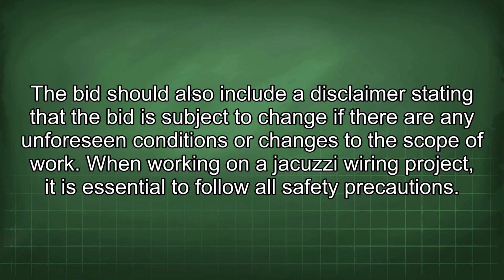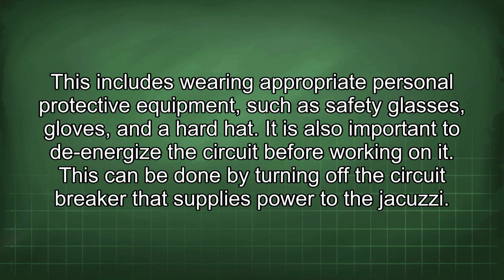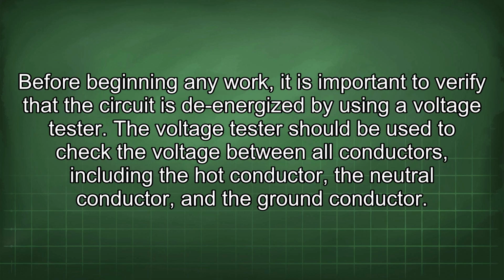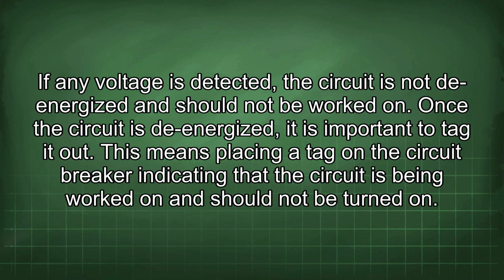When working on a jacuzzi wiring project, it is essential to follow all safety precautions. This includes wearing appropriate personal protective equipment, such as safety glasses, gloves, and a hard hat. It is also important to de-energize the circuit before working on it. This can be done by turning off the circuit breaker that supplies power to the jacuzzi. Before beginning any work, it is important to verify that the circuit is de-energized by using a voltage tester. The voltage tester should be used to check the voltage between all conductors, including the hot conductor, the neutral conductor, and the ground conductor. If any voltage is detected, the circuit is not de-energized and should not be worked on.